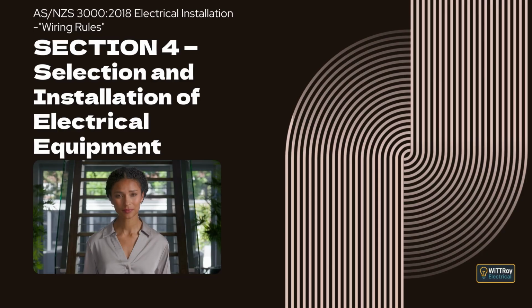Clause 4.3.5, Other connecting devices. This clause explains that where wiring terminates at a junction box, ceiling rose, or similar connecting device for specific equipment, the wiring from that device to the equipment is considered equipment wiring. Clause 4.3.6, Equipment wiring. This clause explains that equipment wiring must be as short as practicable, have a current carrying capacity suitable for the connected load, be protected against short circuit, include a protective earthing conductor where earthing is required, and be selected and installed so that wiring and connections within luminaires are not damaged by heat or ultraviolet radiation. It also explains that smaller conductors may be used where a proper assessment shows protection requirements are met, and clarifies when wiring associated with pendant socket outlets is considered installation wiring rather than equipment wiring.